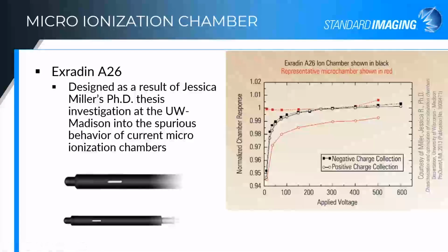In terms of microionization chambers, we've had the Exradin A26 for a little while now, and it has been extremely well received in the field. So this chamber was designed as a result of Jessica Miller's PhD thesis investigation at the UW-Madison, working with the radiation calibration lab there. And she was looking at the spurious behavior, the strange behavior of microionization chambers that existed at the time. Where they would show a wildly different response when you change the polarity of the detector.